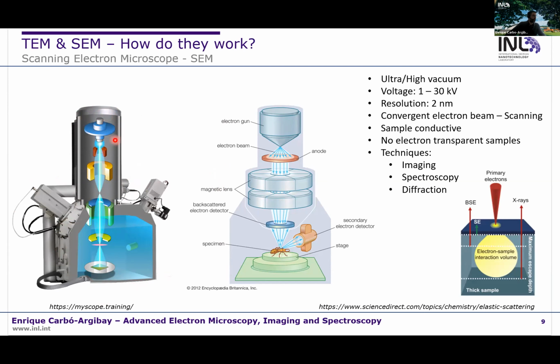We have a source of electrons on top. Then these electrons are accelerated, in the case of the SEM, between 1 and 30 kilo electron volts. And once we accelerate the electrons, then we have several electromagnetic lenses to generate an electronic probe on top of our sample. At the bottom we have our sample. In our case, it can be a biological sample or a material. And we have an electronic probe scanning the sample. This is the reason why we call it scanning electron microscope.